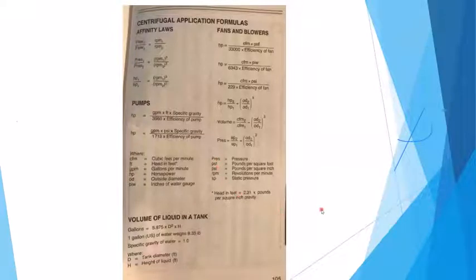What I want to get into now is what we're kind of talking about. My subject today was pumps, and it's very important that we look at pumps. So again, in this little book, it's got the calculation of horsepower, GPM, pump efficiency, but you can also reverse it and actually calculate the pump efficiency. So you can look at the horsepower, how many GPM it's going through, and get to the point where we can do a pump efficiency evaluation.